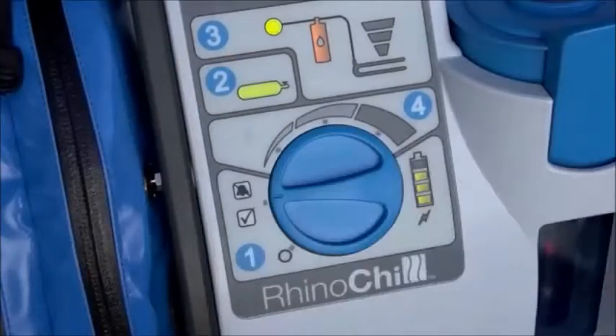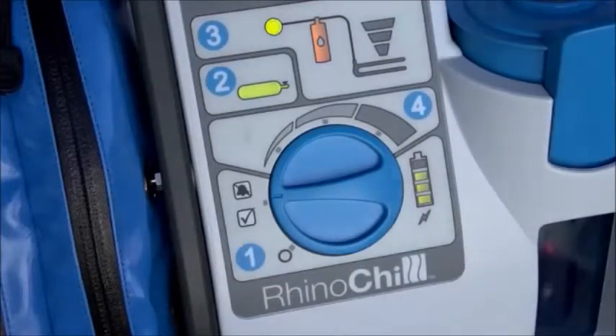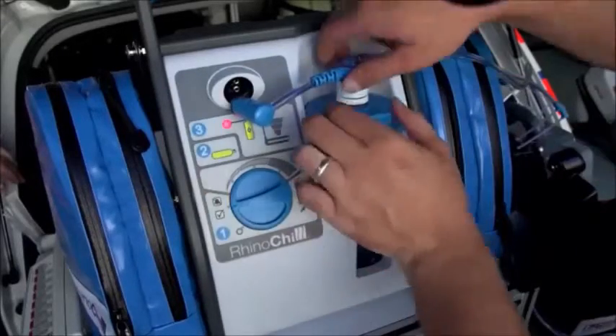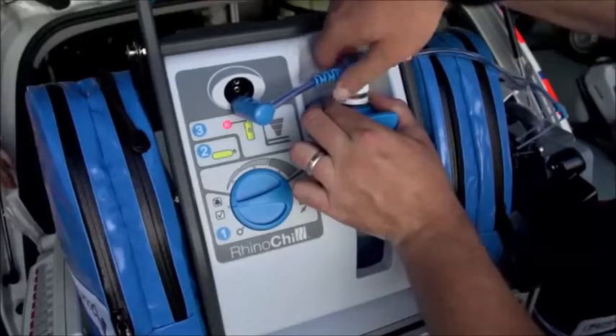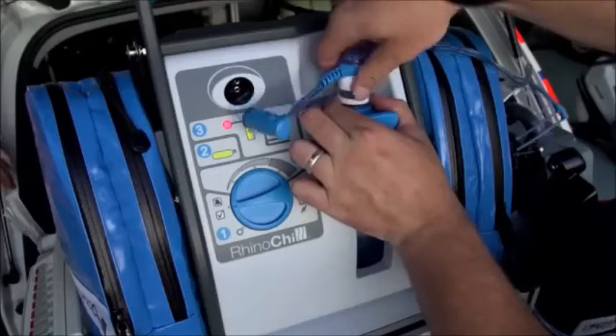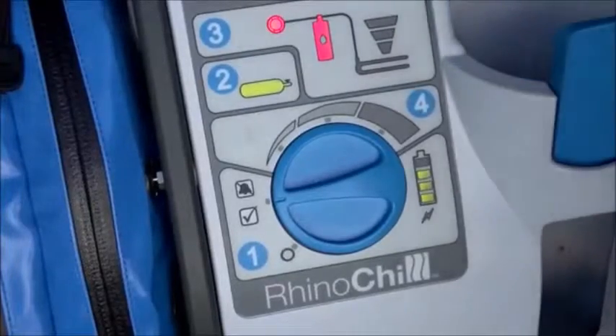Changing the coolant bottle while the patient is undergoing treatment is a rapid and simple task to perform. First, ensure the setting control knob is in the checked position. Note this will ensure the coolant out alarm is muted during bottle replacement. Note, the check position is also the alarm muted position. Unscrew the bottle interface from the coolant bottle and remove the empty bottle from the bottle holder. The coolant icon should be illuminated red.